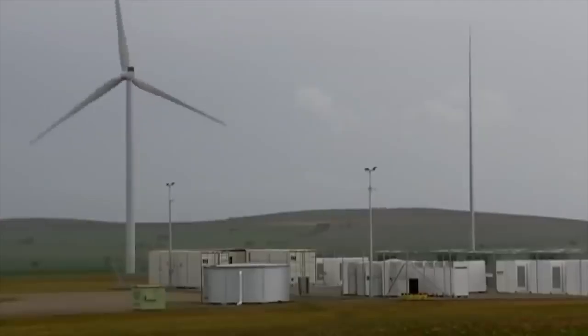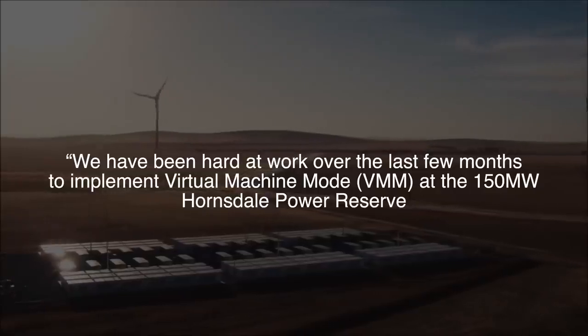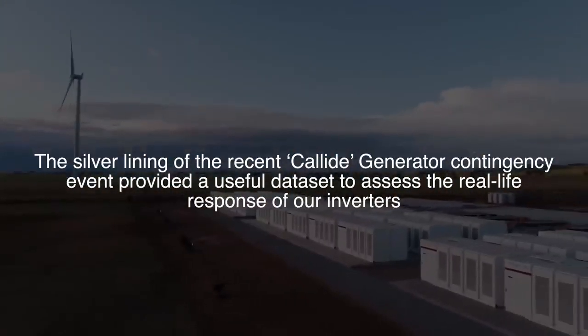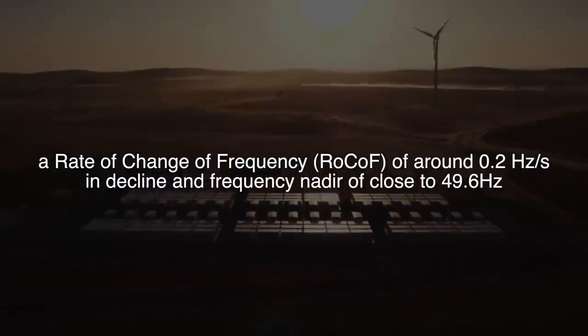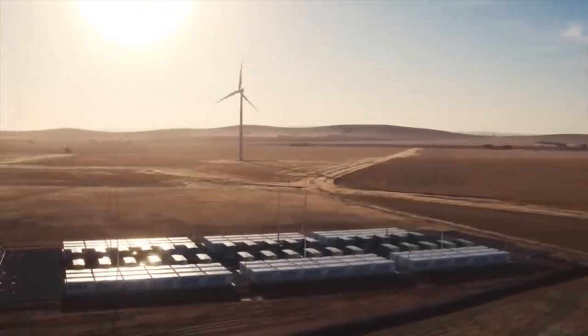Joseph Tadic, senior manager of engineering at Tesla, hosted the webinar and said that batteries can be customized for specific network conditions. This particular response was provided in parallel with traditional primary frequency control, energy market dispatch, and black start services. In a LinkedIn post, Tadic wrote: 'We have been hard at work over the last few months to implement virtual machine mode at the 150 MW Hornsdale Power Reserve. The silver lining of the recent Callide generator contingency event provided a useful dataset to assess the real-life response of our inverters — a rate of change of frequency of around 0.2 Hz per second in decline, and a frequency nadir of close to 49.6 Hz.